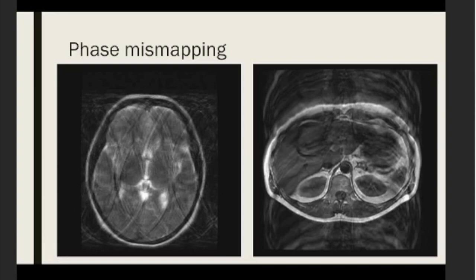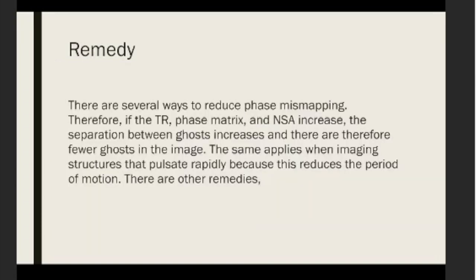Now we'll look at how to fix or reduce phase mismapping. There are several remedies depending on how the artifact occurs. If repetition time, phase matrix, and NSA are increased, the separation between ghosts increases but there are fewer ghosts in the image. This same principle applies when image structures pulsate rapidly, as that reduces the period of motion.